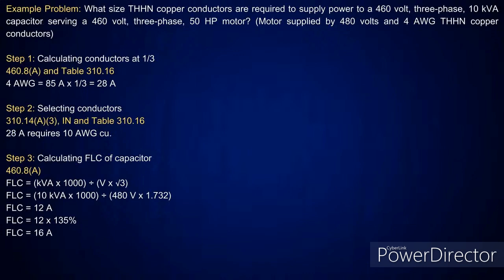Now, like this, and this is where I've got a capacitor. Okay? I've got a 460 volt 3-phase 10 kVA capacitor, and it's going to serve a 460 volt 3-phase 50 horsepower motor. Okay, and we're already giving you the information here. The motor is supplied by 480 volts, and it has number 4 THHN copper conductors. All right, so if I look at a number 4 conductor and I go over and pick up Table 310.16 and come down the 75 degree C column, it's going to tell you it's good for 85 amps.